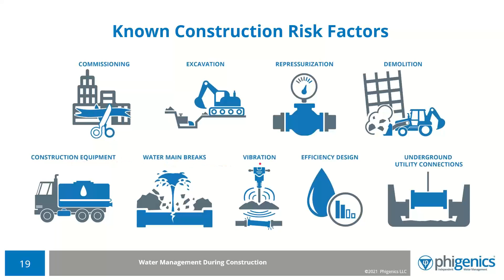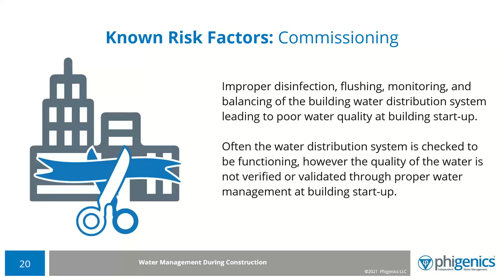These are the known factors. At commissioning, at that building startup, we found there was an improper process of disinfecting and flushing protocols, and there was no monitoring. Nobody seemed to know what was going on, yet the building would open, disease cases would start to emerge or be assigned to the building, and people wouldn't know where it was coming from. It would be a chaotic experience and a lot of liability in situations like that. If there was a uniform process of water quality, this would cut down on that. So we need people that are going to have this process in place and check that the functioning and the water quality is verified and validated through that specification and process.